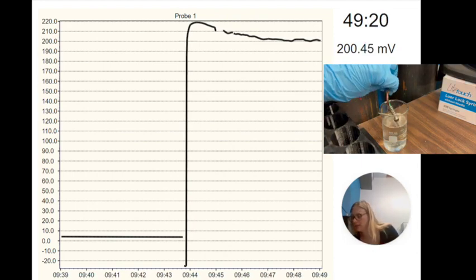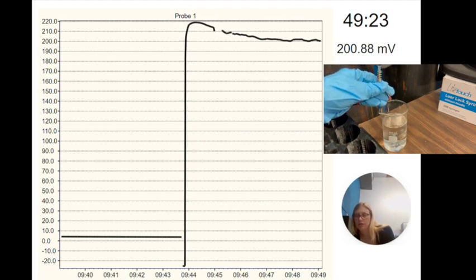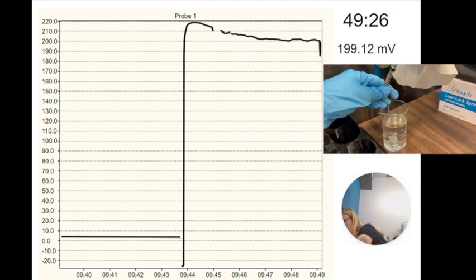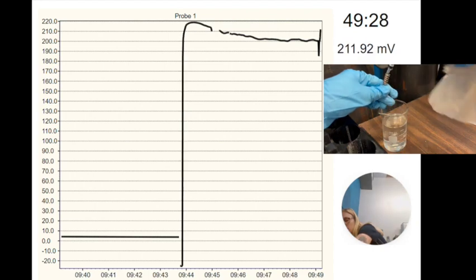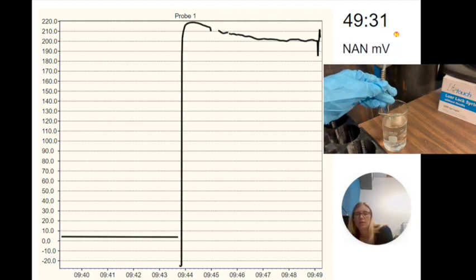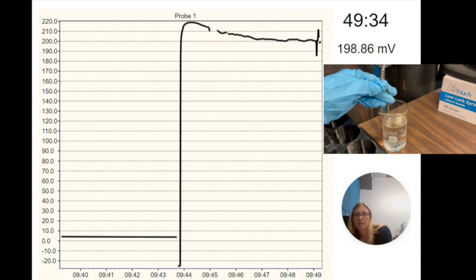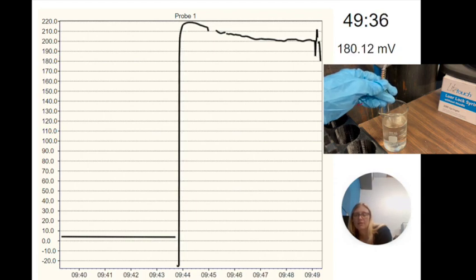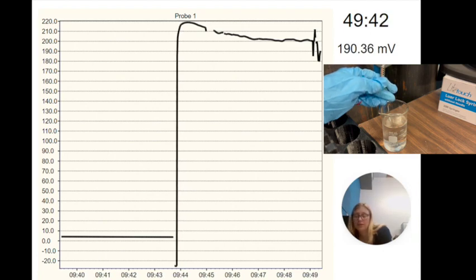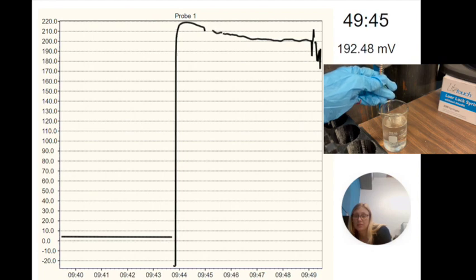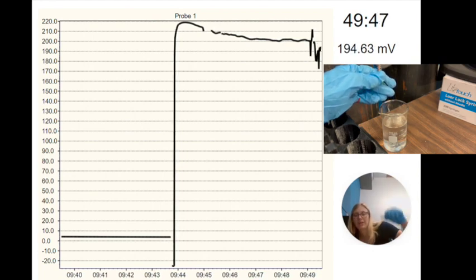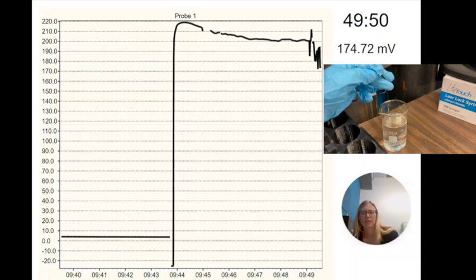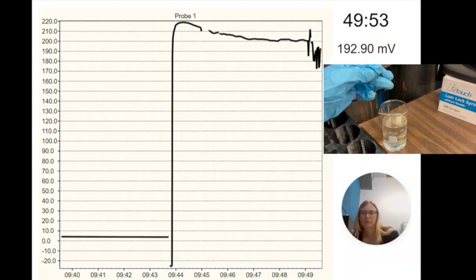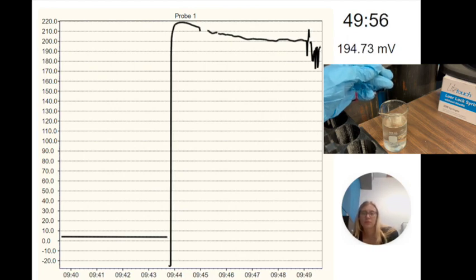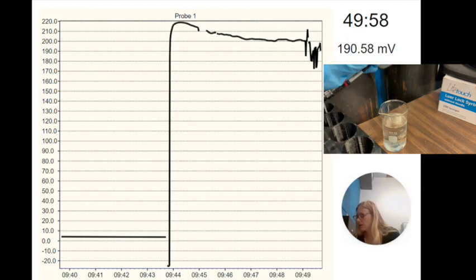Then if we take the sensor out of water and try to dry it off, we notice that it spikes around and it is not responding consistently. So it's going up and down, reading all over the points. So this would be a damaged and unusable sensor.